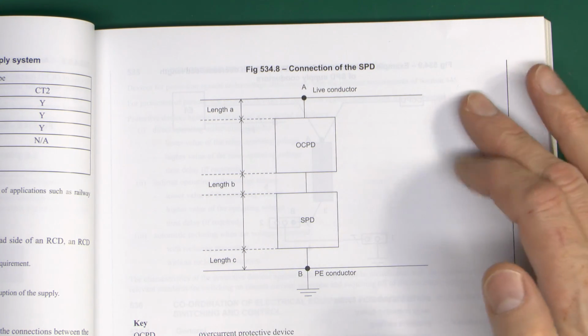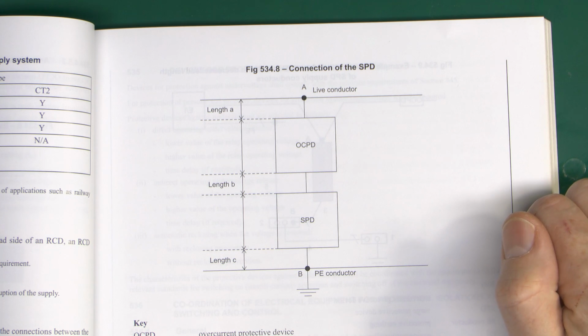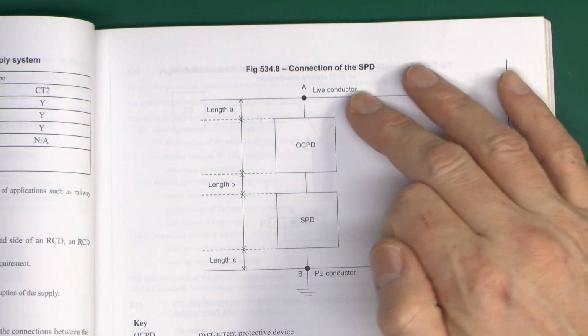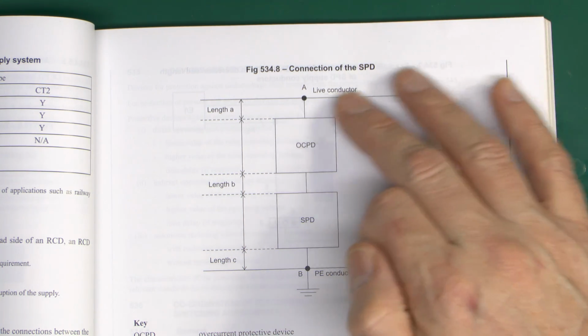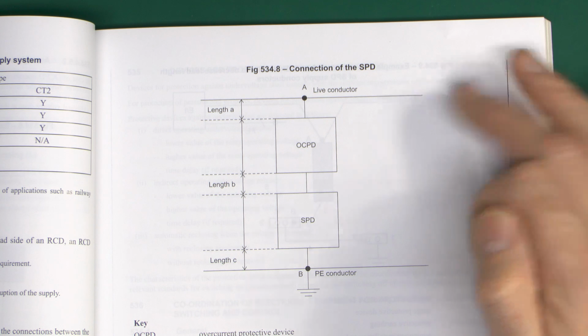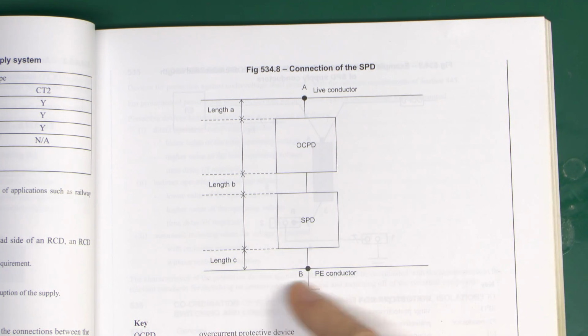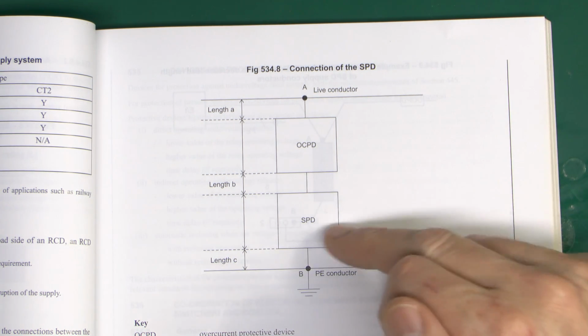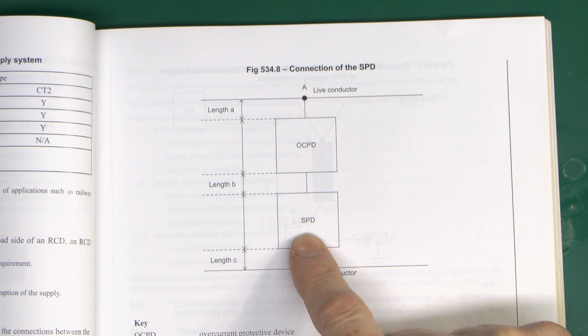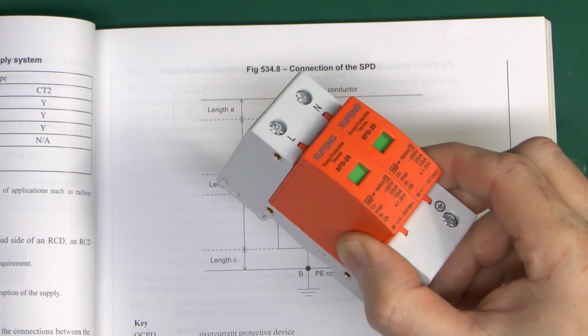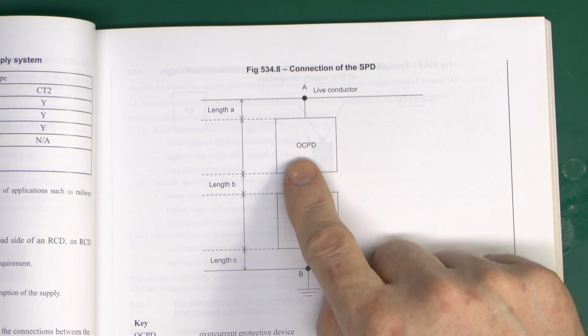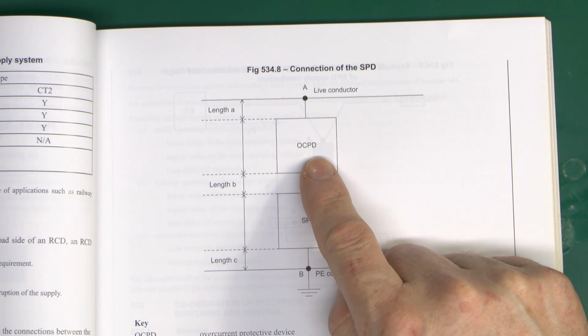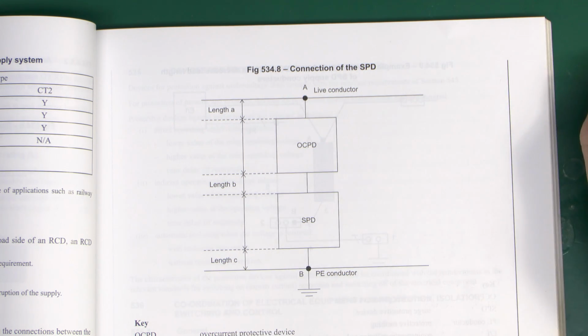Now I've got this diagram here, 534.8, and this shows a theoretical connection of a surge protection device. So we've got the line conductor here, or the live conductor. Live could of course be line or neutral, and the protective earth conductor here at the bottom, and then between those we've got the surge protective device, which is basically one of them, and we've also got the overcurrent protective device, which is going to be a fuse or circuit breaker or something like that.